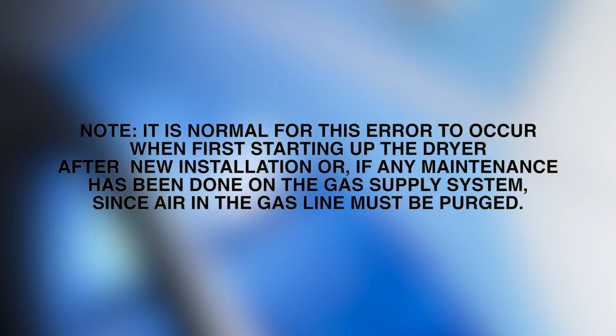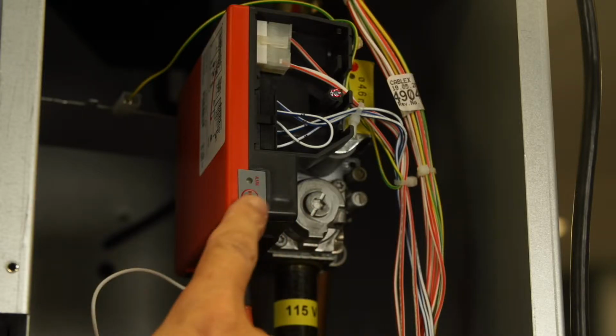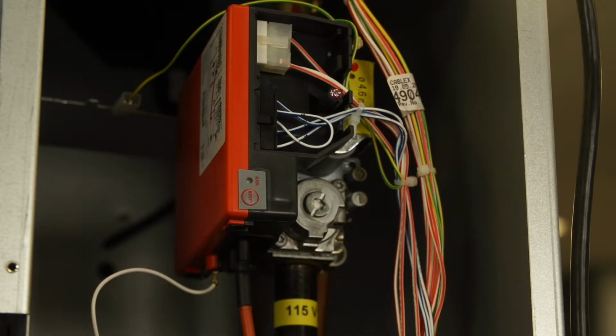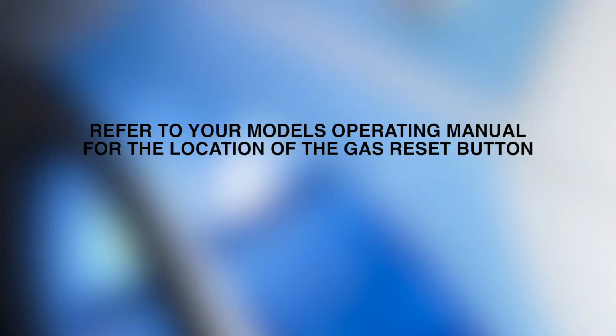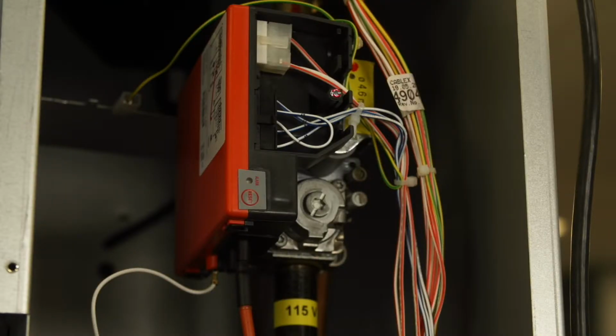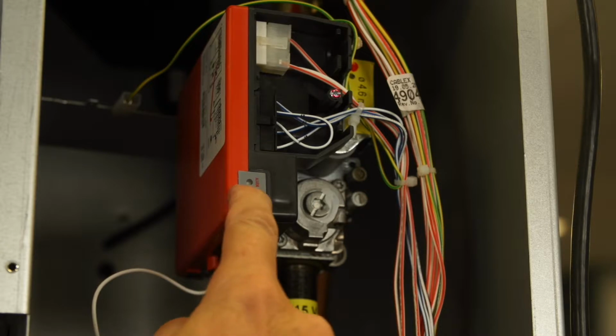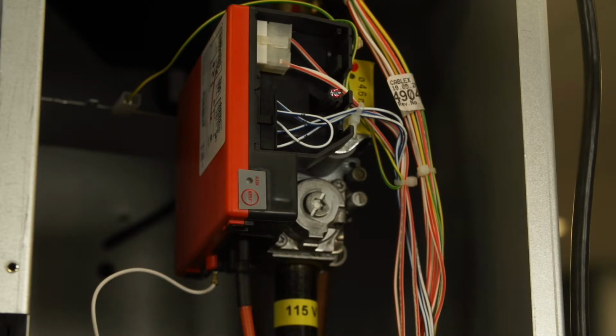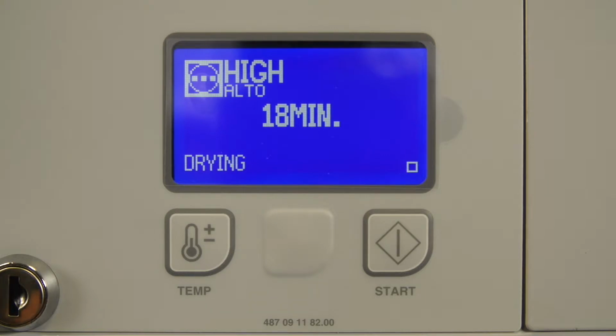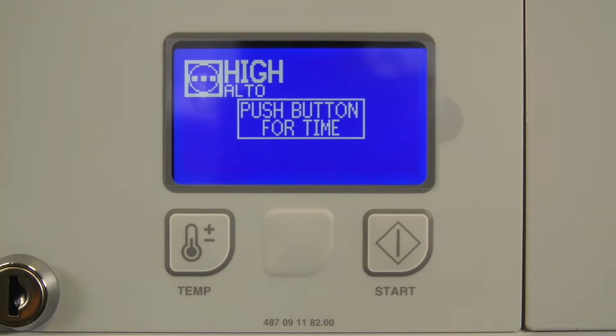Note, it is normal for this error to occur when first starting up the dryer after either new installation or if any maintenance has been done on the gas supply system, since air in the gas line must be purged. In this case, when this error occurs, it must be manually reset by pressing the gas ignition reset button on the dryer's controller. Refer to your model's operating manual for the location of this gas reset button. Open the operating panel and press the gas reset button on the back of the control PCB for 1 second.